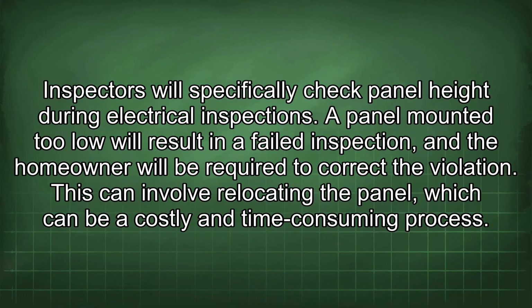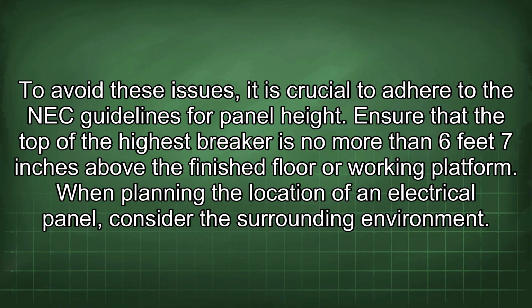Inspectors will specifically check panel height during electrical inspections. A panel mounted too low will result in a failed inspection, and the homeowner will be required to correct the violation. This can involve relocating the panel, which can be a costly and time-consuming process. To avoid these issues, it is crucial to adhere to the NEC guidelines for panel height.